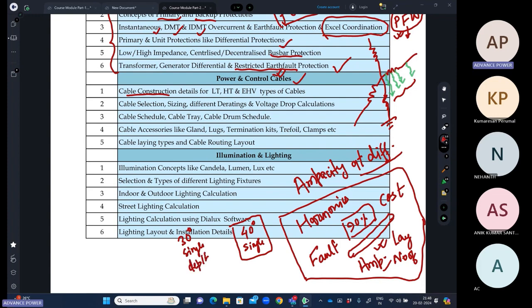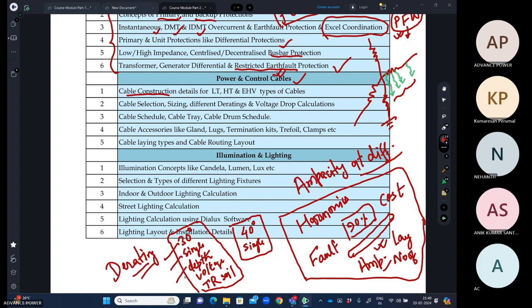Here it is important at what depth you are laying. Again, it is important at what voltage level you are laying. What is the voltage level of the cable? What is the thermal resistivity of the earth, the soil? All these parameters will be fixed by the manufacturer and they will provide you the derating. If you are changing from these parameters, then the derating will be applied and the final ampacity will be calculated. So these are the design engineer's job.